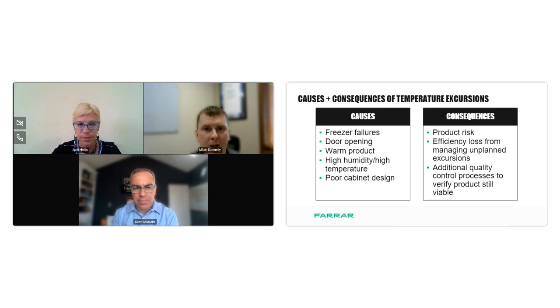If you have warm ambient conditions or high humidity, humidity can lead to ice buildup inside of the freezer, but high ambient also makes the refrigeration system have to work harder. It's not as easy for it to reject its overall heat out of the system, and so it's working harder and may not be able to maintain temperature depending on how it was designed. And then if you get into overall design of the cabinet, if the cabinet's not designed very well, or there's lots of gaps or seams, or maybe it's poorly manufactured, that can lead to air infiltration into the freezer, which then impacts the temperature uniformity inside the product.